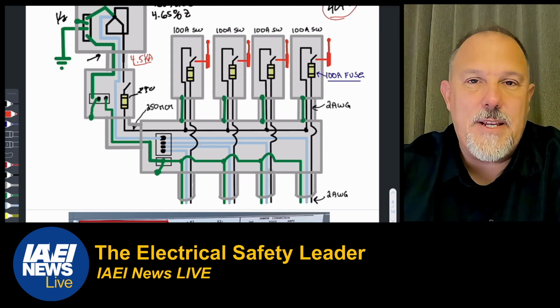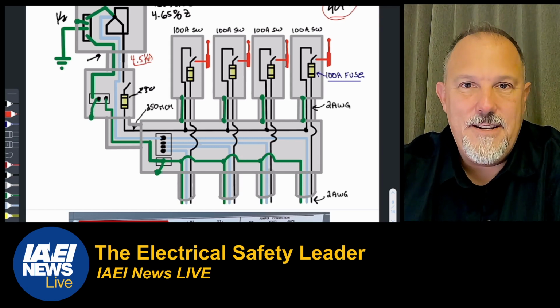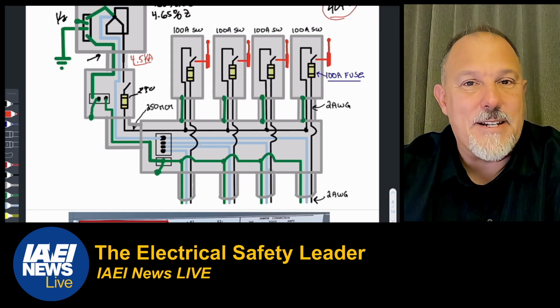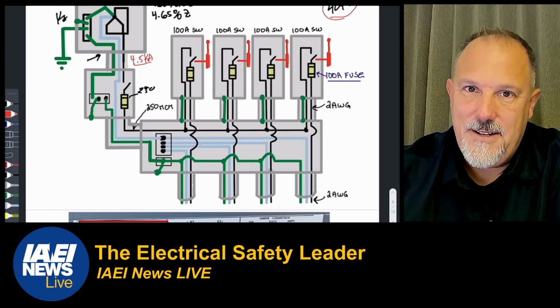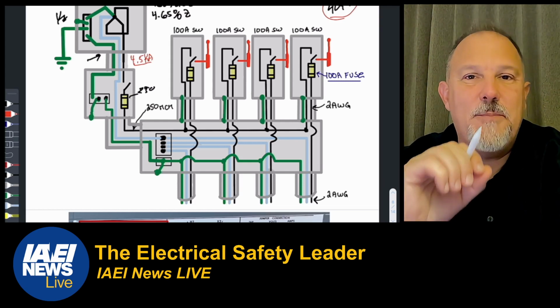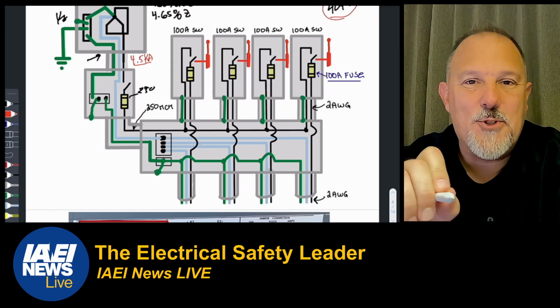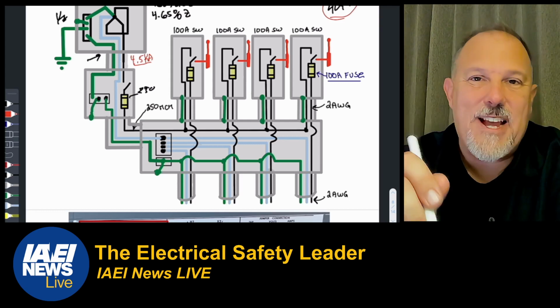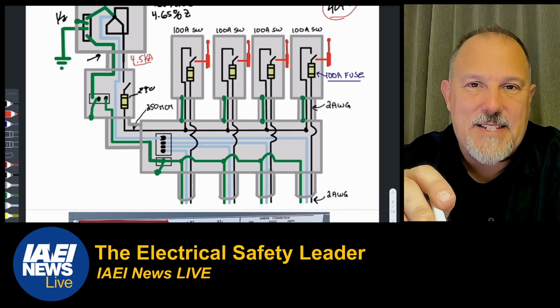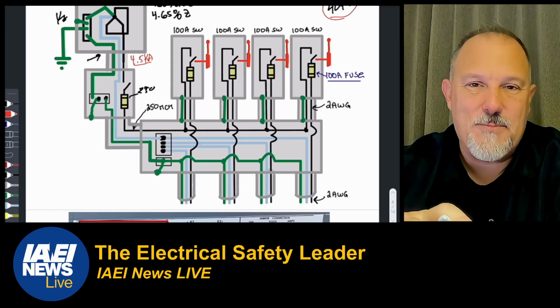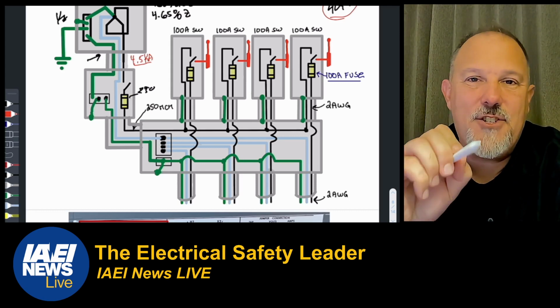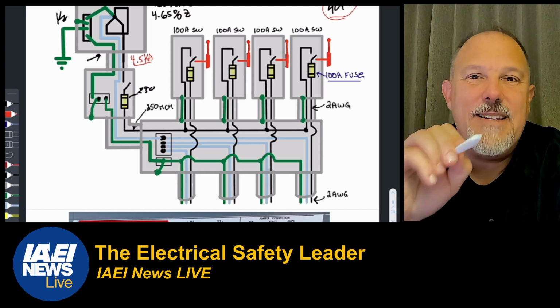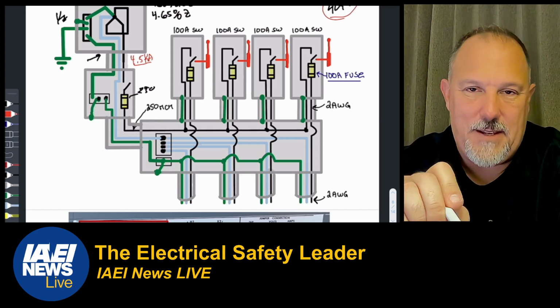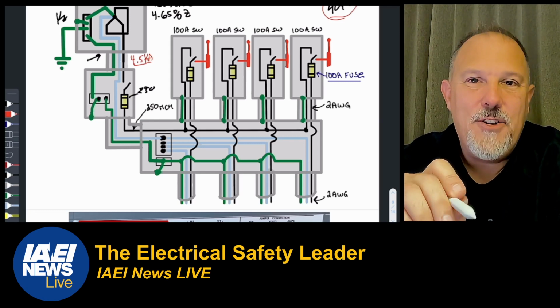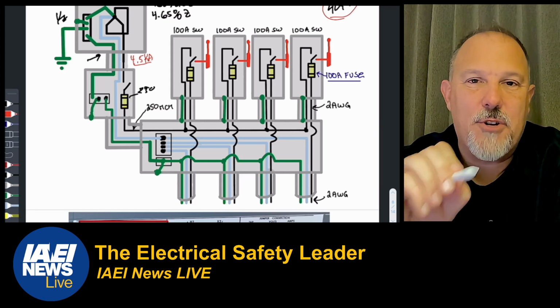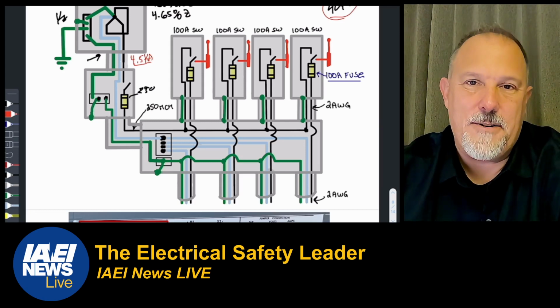And what is that doing? It's intentionally putting current on the equipment grounding conductor, although it's milliamps. But those are called objectionable currents. Go into Article 250 and tell me down in the chat, in the comment section on this video. I know it's recorded, but put in the comment section what section in Article 250 tells you you cannot have objectionable currents on the equipment grounding conductor.